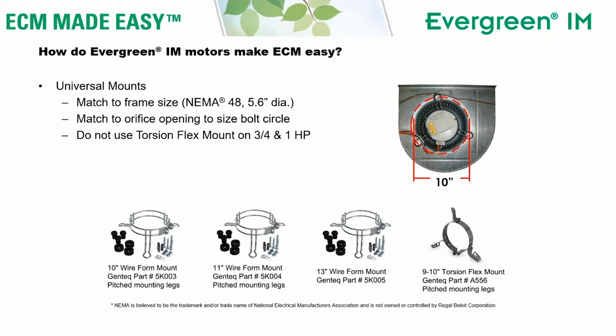If the motor you're taking out has any other kind of mount, welded legs or resilient mount, mounts around the bearing ends, then you'll need a new universal mount. And we have various sizes of mounts, all built for 48 frame motors. The easiest way to know what size mount you need is to measure the air opening around the motor. So measure the diameter of the air opening around the motor. In the example on screen, it's 10 inches. So if I've got 10 inches of airspace, I need at least an 11-inch mount.